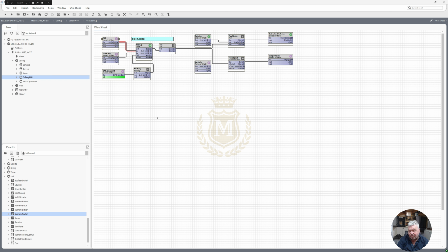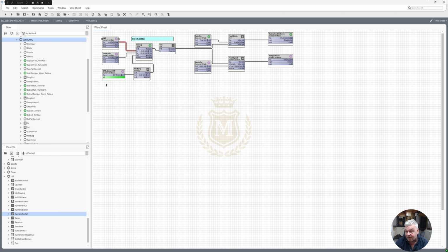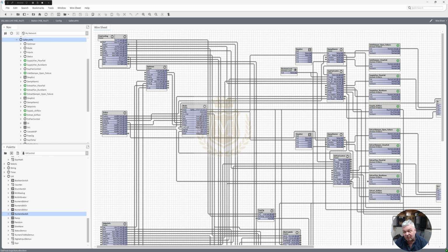But with the AHUs, there's a lot of logic, as you can see just by looking at this gallery logic that I was showing you right at the beginning. It's not just down to free cooling. There's a lot. The external fan control on pressures, supply fan control on pressures, dampers, alarming if your damper doesn't open. That was the free cooling folder that we just did. There's so much. You've got your emergency stops. But there's a lot more to it, and of course all your set points. D-hum set point there, RH set points.